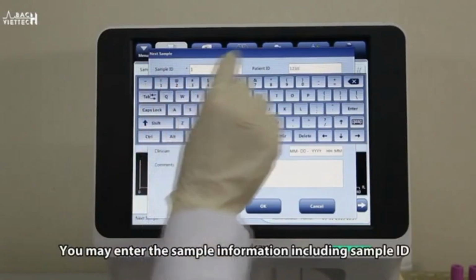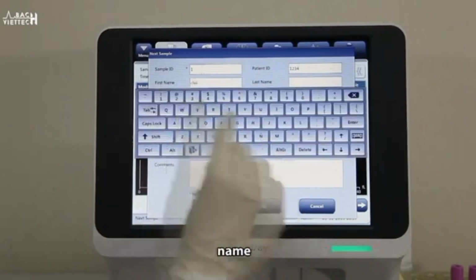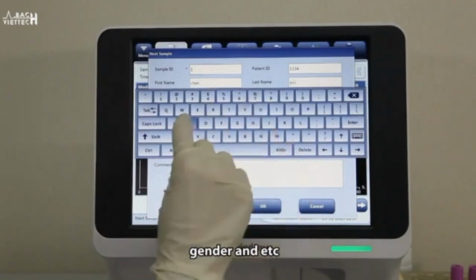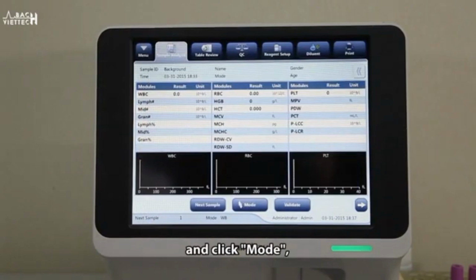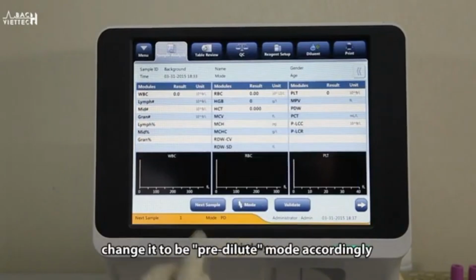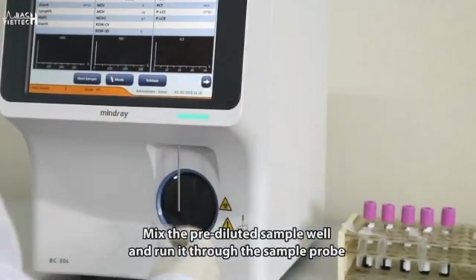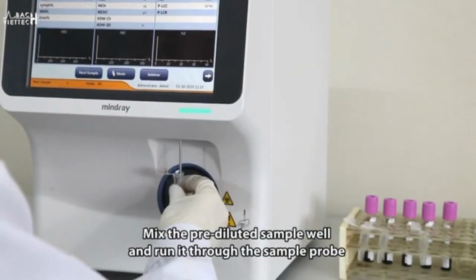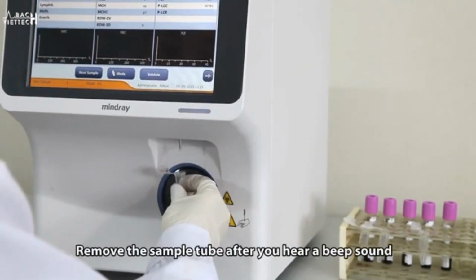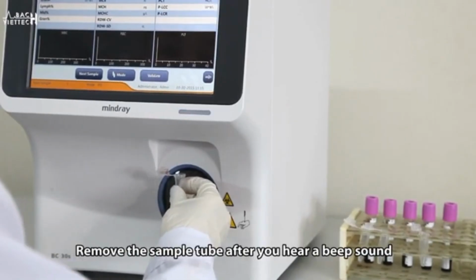You may enter the sample information including sample ID, name, age, gender, and etc., and click Mode. Change it to be pre-dilute mode accordingly. Mix the pre-diluted sample well and run it through the sample probe. Remove the sample tube after you hear a beep sound.